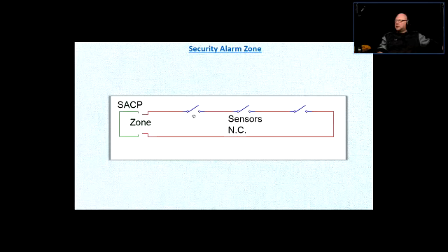And if the system is at rest, all the switches are going to be closed. So there's going to be a closed loop. If one of them detects motion, it just takes one of them to open, and the whole loop is open. So that's in series. Same as you can put the door contacts on windows. And if, for example, in a living room all the windows are closed, then all the switches would be closed.